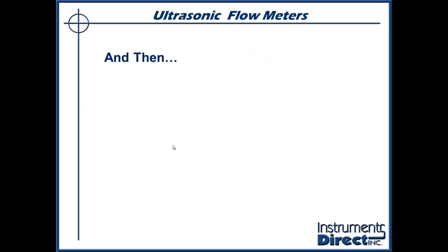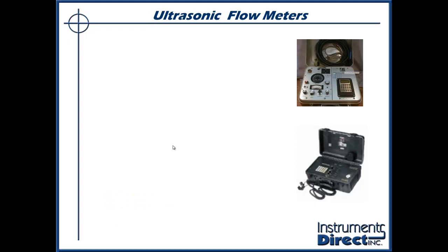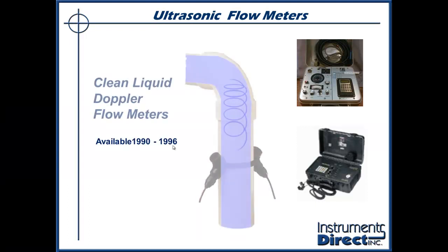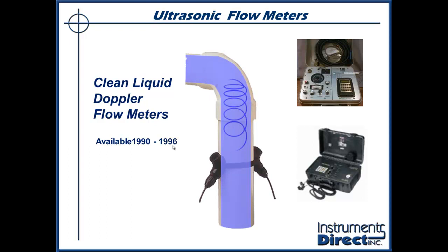Back in the old days when Doppler flow meter manufacturers were trying to keep up with transit time technology, Polysonics and Dynasonics came out with something called a clean liquid Doppler. These devices were only around in the early 90s. Basically, they put a hearing aid on an ultrasonic Doppler and placed sensors at a 90-degree elbow to reflect off turbulent flow. They weren't very accurate — it was a stepping stone from Doppler to transit time technology. They are not around anymore. Cross clean liquid Dopplers off your list.